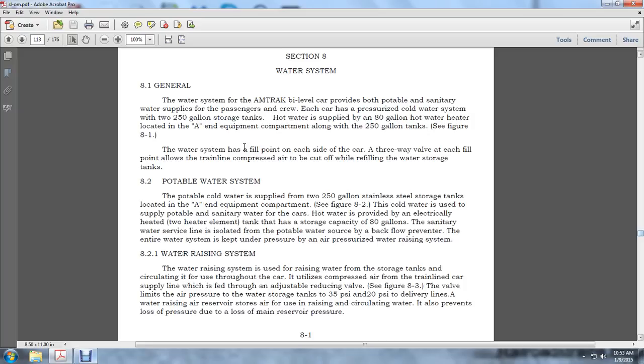The hot water is provided by an electrically heated tank with two heater elements and a storage capacity of 80 gallons. The sanitary water service is an isolated potable water source, with a backflow preventer to keep it from entering the entire water system. It is kept under air pressure by the water raising system. 8.2.1, the water raising system.